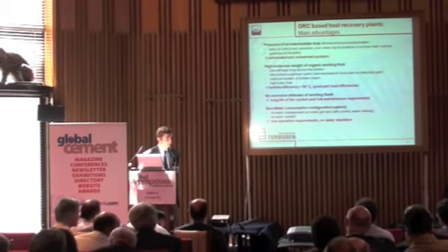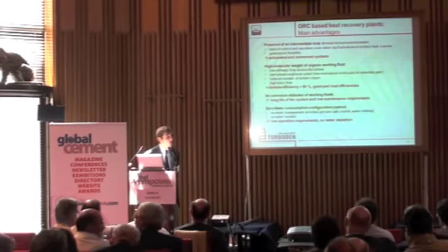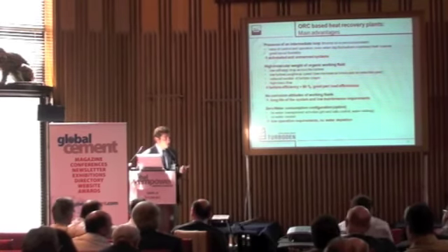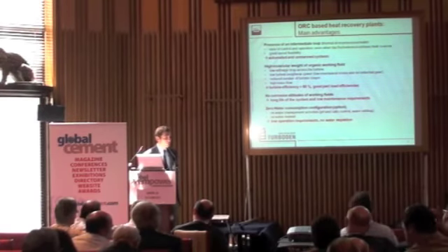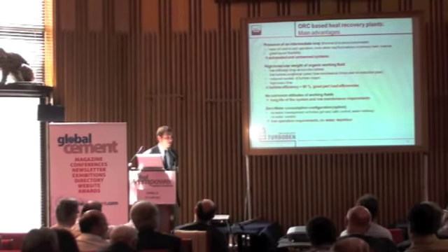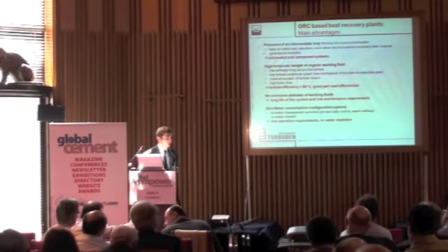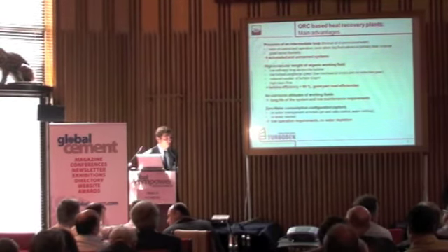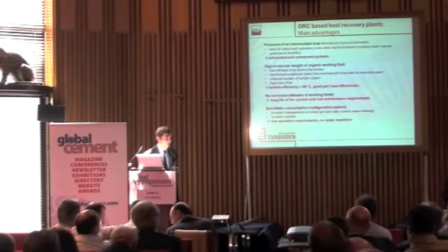Yes. So it's the cost of thermal oil. There are two organic fluids. One is thermal oil. Very typically, if properly managed, no thermal oil is lost, and up to 1% of the total content per year can be changed, but we're talking about a negligible cost, maybe a couple of $1,000s per year. Working fluid is even less, so fluid-wise, the cost of replacement is just negligible.